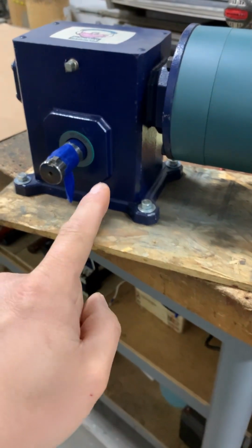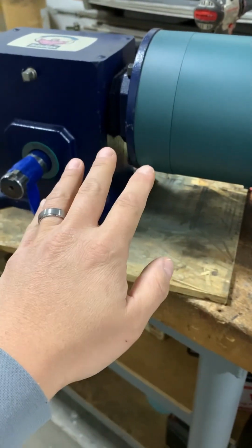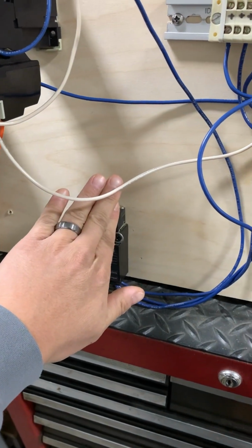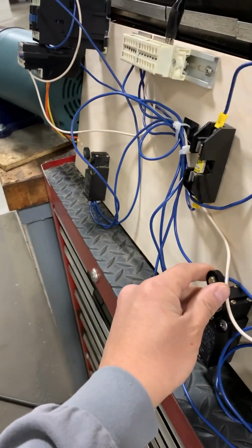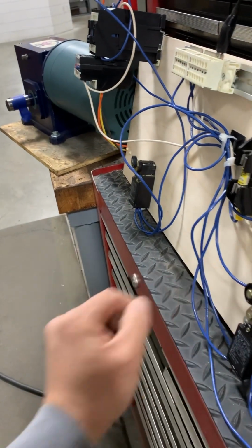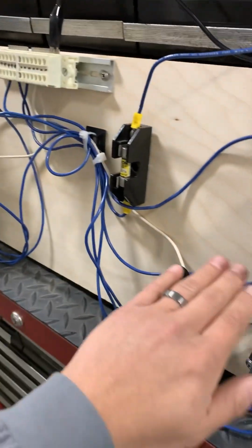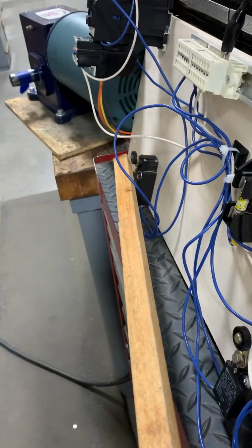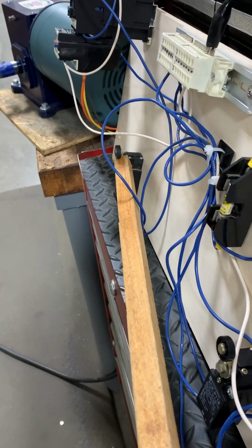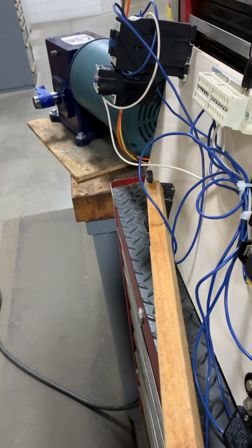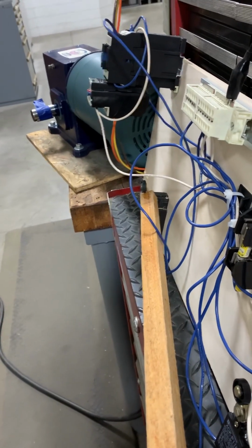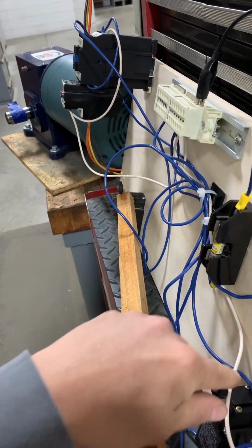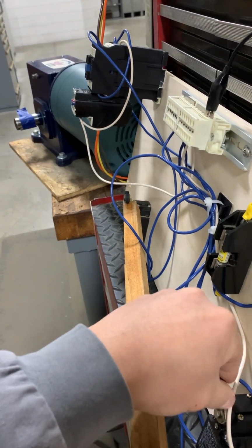And now let's observe the scenario where we do not want this electric motor system to start up when we have product at the end of the line of the conveyor. So let's go ahead. We start up our conveyor. So product makes its way, it starts it up, and it's now continuing down the line. Now it makes its way to the end of the line. It hits that limit switch, and now the conveyor stopped. If the next product would come and hit this limit switch, we cannot start it up.